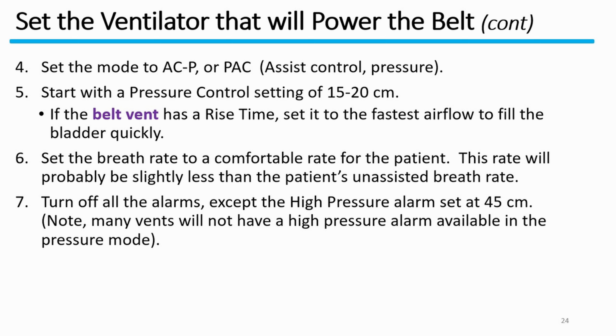If the belt vent has a rise time, set it to the fastest airflow to fill the bladder quickly. Set the breath rate to a comfortable rate for the patient. This rate will probably be slightly less than the patient's unassisted breath rate. Turn off all the alarms except the high pressure alarm set at 45 centimeters. Note, many vents will not have a high pressure alarm available in the pressure mode. Turning off all the alarms except for the high pressure alarm will help reduce distraction and annoyance during the titration process. Set the inspiratory time.